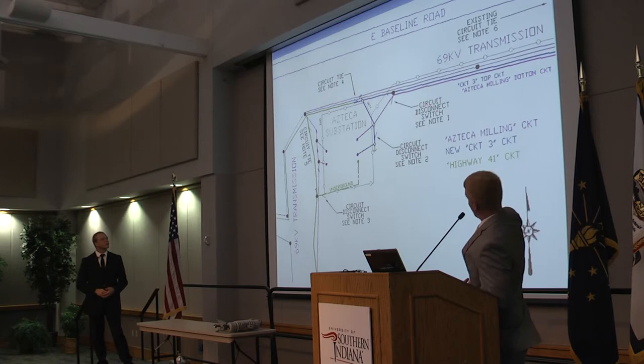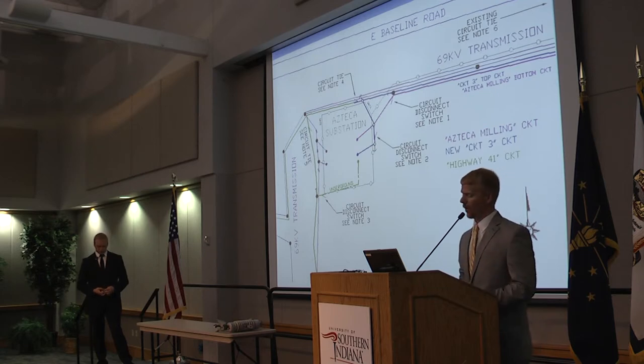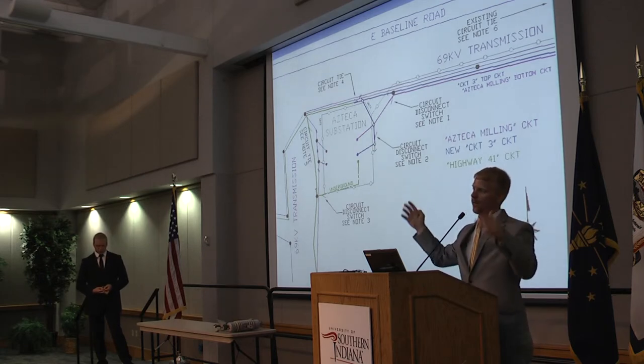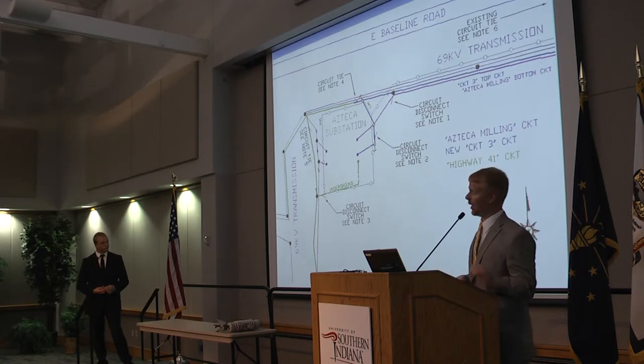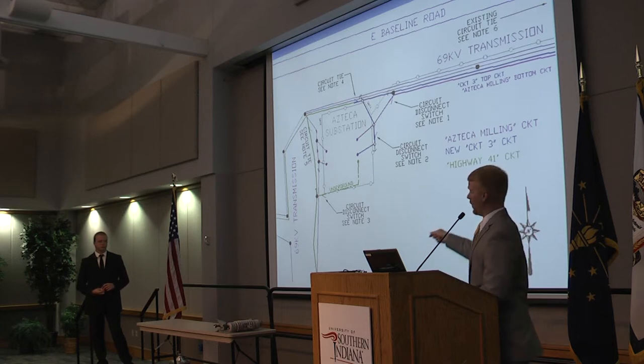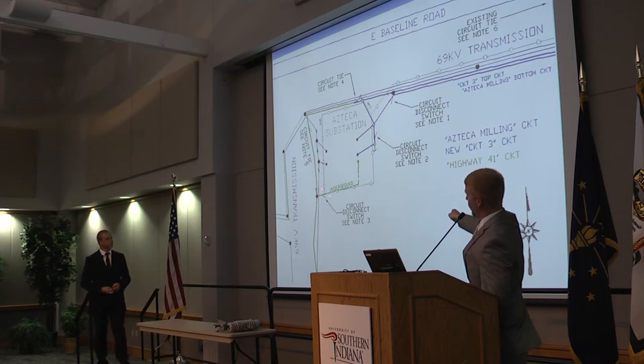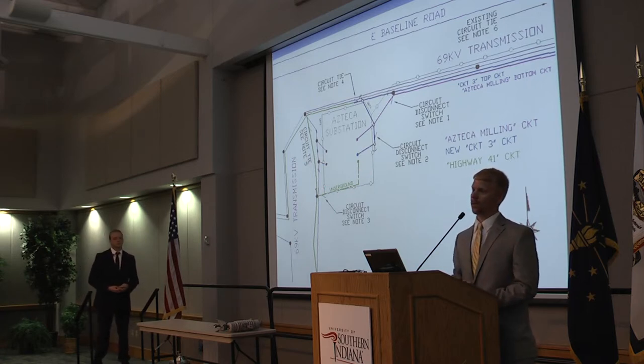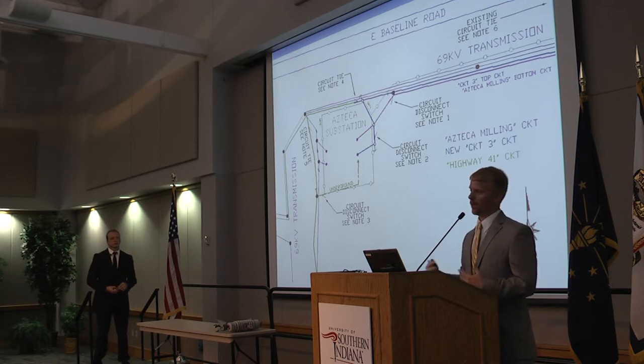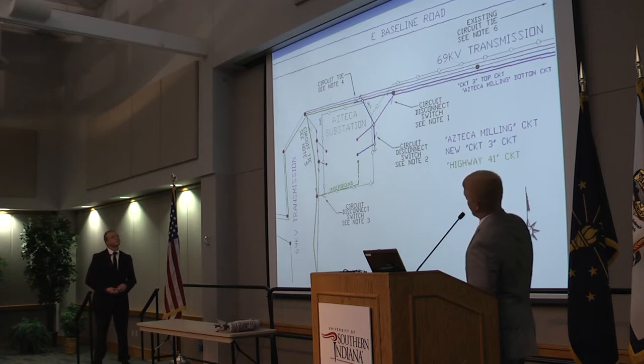I have notes on the drawing. Notes 1, 2, and 3 are gang operated switches, which is a large rack that operates all three phases and the neutral at the same time. Basically they're circuit disconnect switches. If maintenance is needed, the crew can go out and open one of these switches and kill everything upstream or downstream of that fuse, so that whatever needs work can be in a de-energized state, which is much safer, and cheaper because they don't have to blanket everything. Notes 4, 5, and 6 are circuit ties.